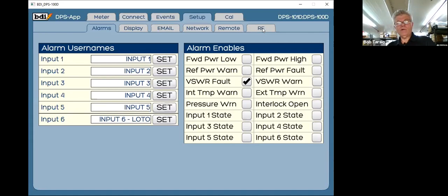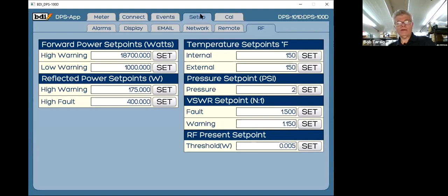So we had to use reflected power for that - that's how we got started with it. But a lot of customers asked us, 'we really want VSWR,' so we added that now. If you go into the RF setup page, you can set a fault for VSWR, and on the remote page, you can select whether you want it to trigger on VSWR or reflected power. If you deselect it, it's reflected power; if you set it for VSWR, it's VSWR. Otherwise the meter operates pretty much the same way.